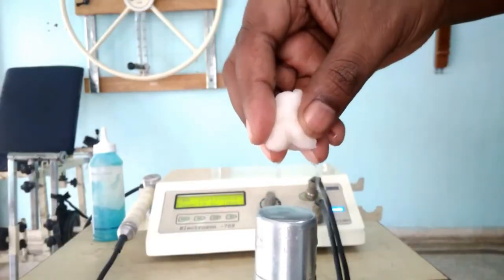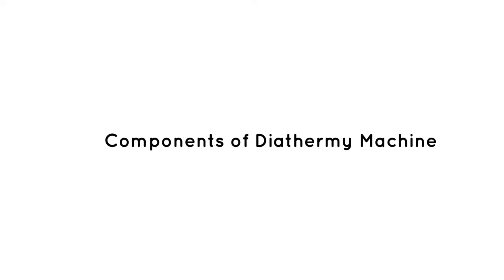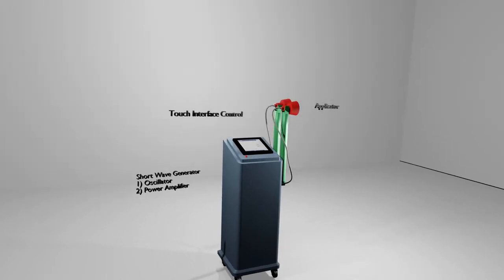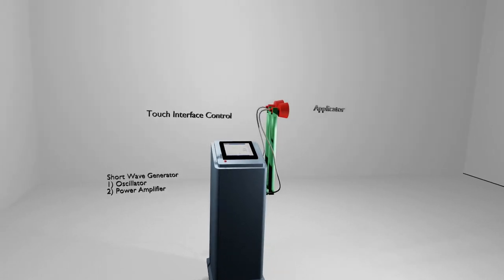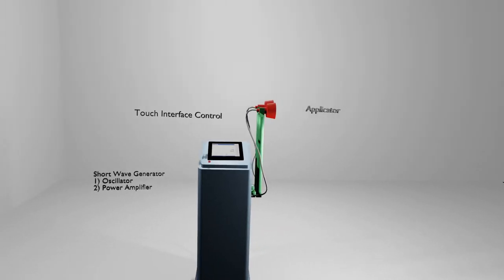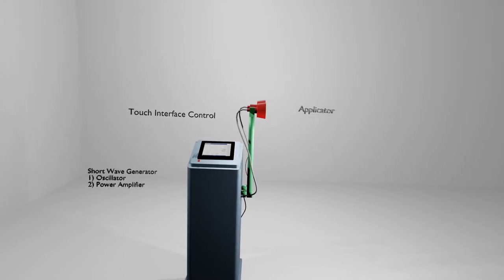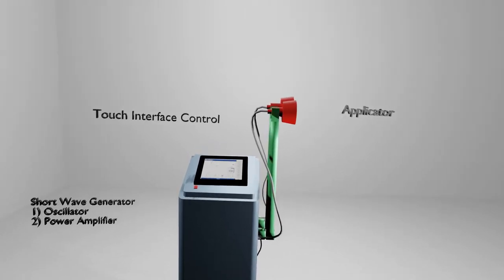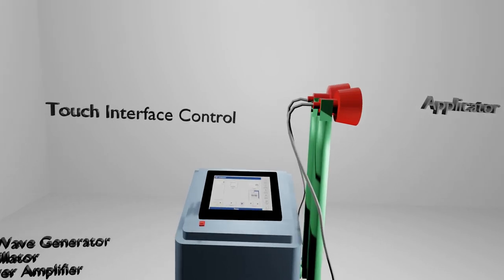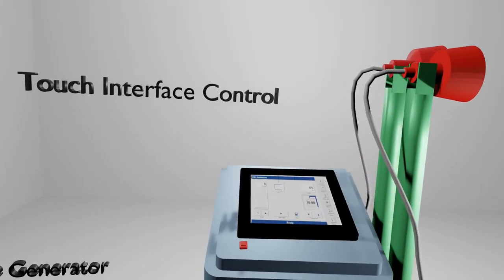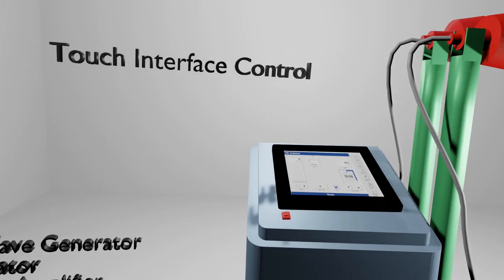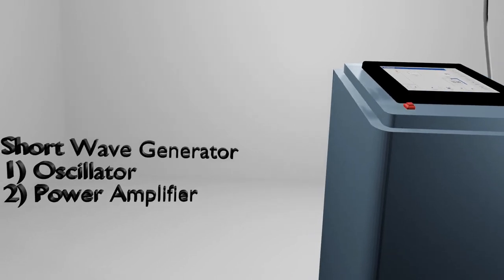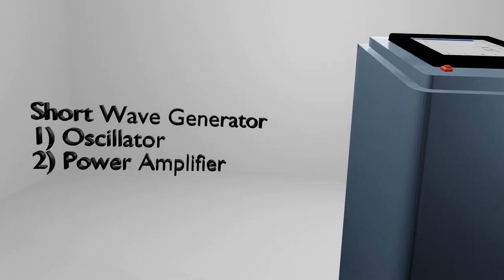All shortwave diathermy units contain three parts: the oscillator, the power amplifier, and the applicator. The oscillator, not unlike one found in a radio transmitter, generates the 27.12 MHz or 13.56 MHz signal that the power amplifier boosts. The oscillator usually employs a timer to control the duration of treatment. The power amplifier boosts the oscillator's output to therapeutic levels, and its circuitry contains a means to adjust the output power along with a meter or other output power indicator.